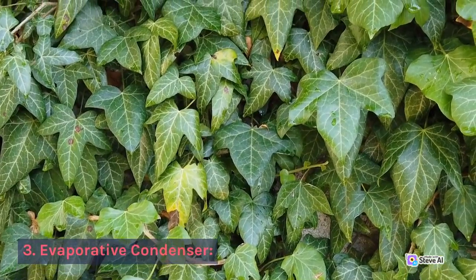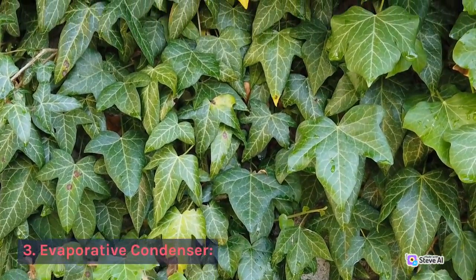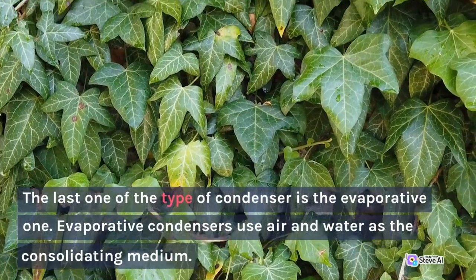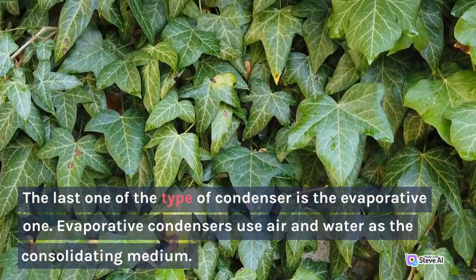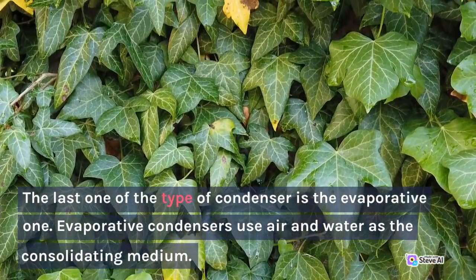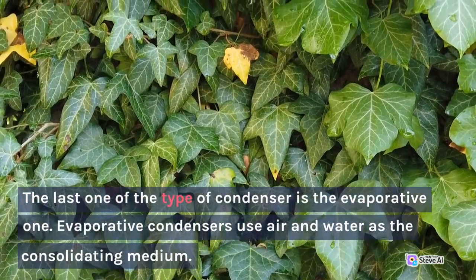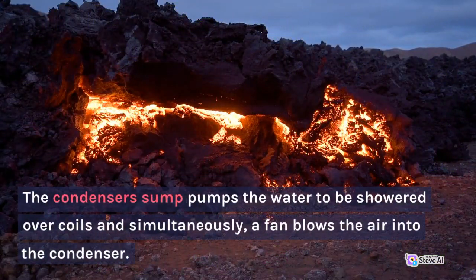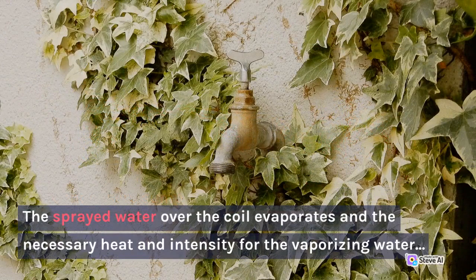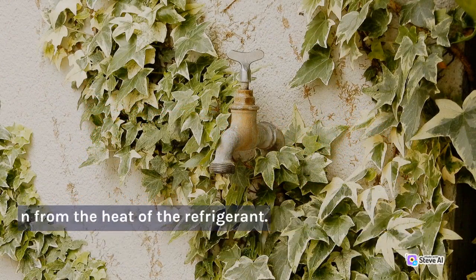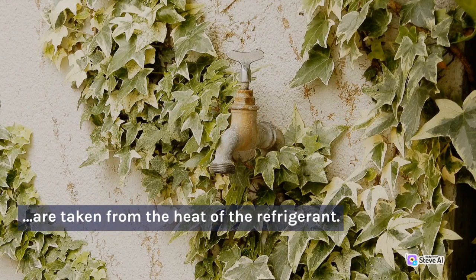3. Evaporative condenser. The last type of condenser is the evaporative one. Evaporative condensers use air and water as the condensing medium. The condenser sump pumps the water to be sprayed over coils, and simultaneously, a fan blows the air into the condenser. The sprayed water over the coil evaporates, and the necessary heat and intensity for the vaporizing water are taken from the heat of the refrigerant.